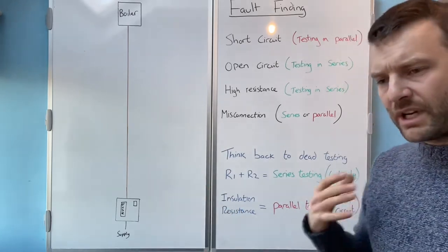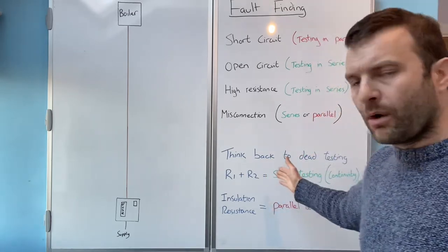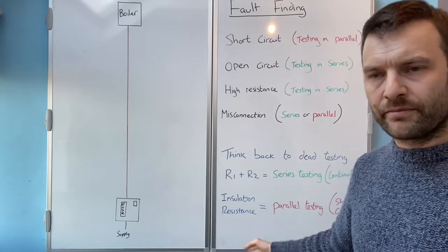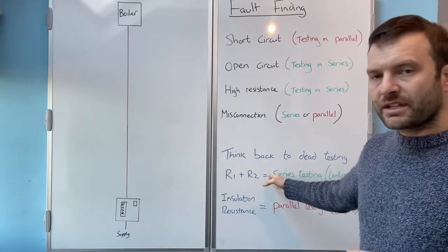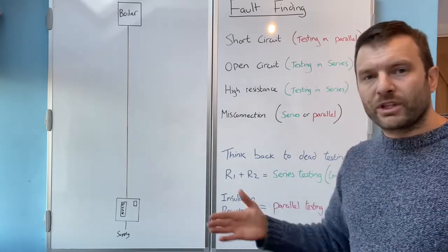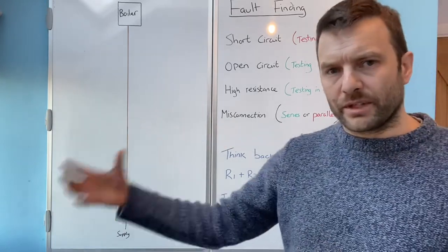So if you get really stuck, okay, think back to R1, R2 testing and insulation resistance testing. With R1, R2 testing, we want continuity. With insulation resistance, we don't want continuity. And it's as simple as that. And we do that before we put it into service.